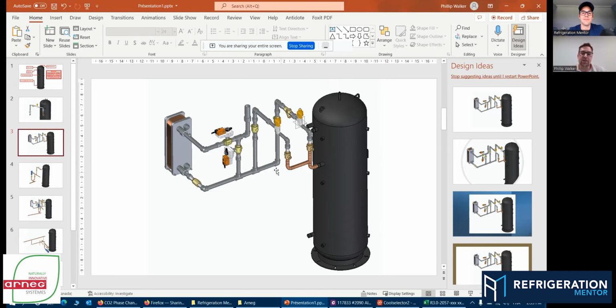And we thought we can make something a lot better. About 24 months ago, we said, this is so critical. For the cost of just adding this line, it's insignificant. It was actually costing us more money if we looked at maintenance and serviceability if this valve failed, theoretically, than adding the secondary valve. So we added it in. It's a safety feature, all our systems. And I know a lot of people. I love that, Philip, because that's another game changer. You're willing to put more money into the system, costing you more money to help your customer out in the long run.